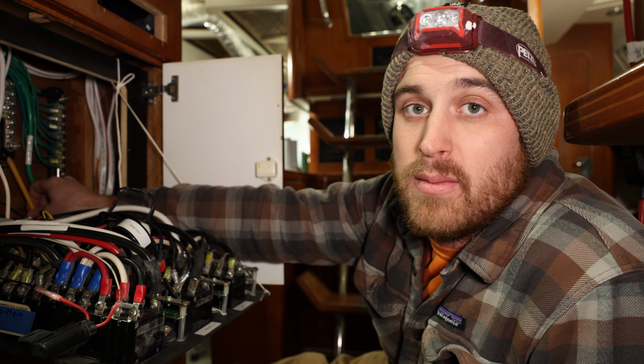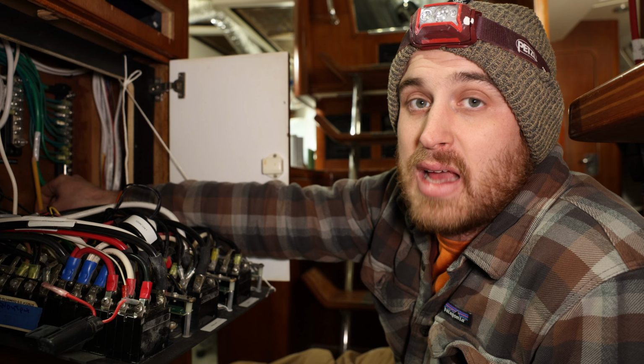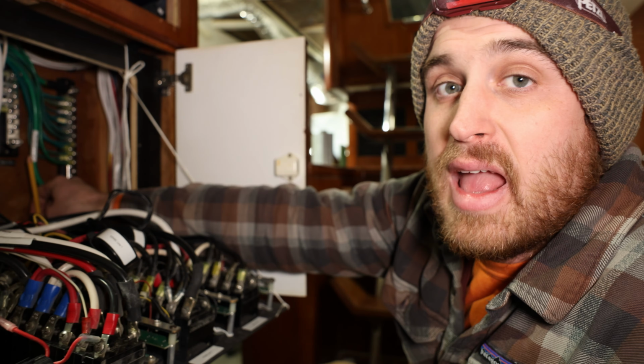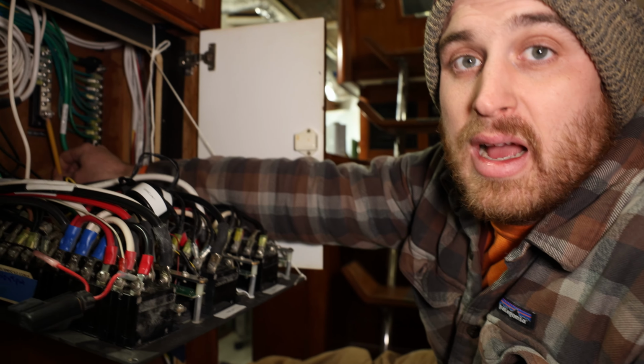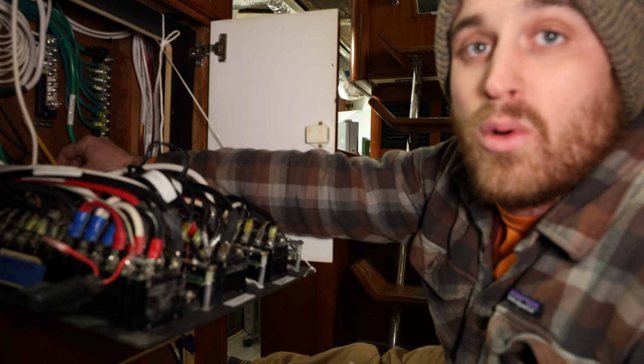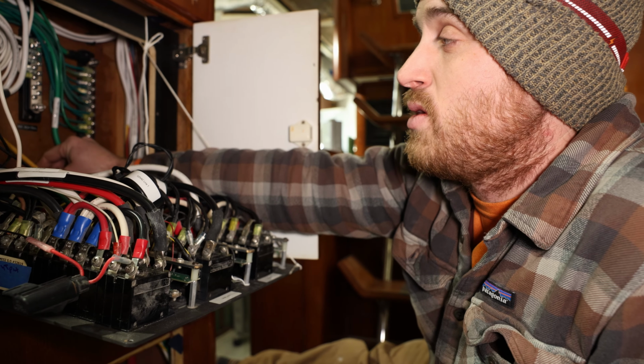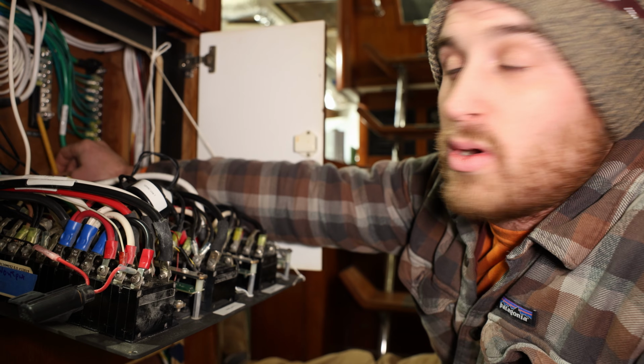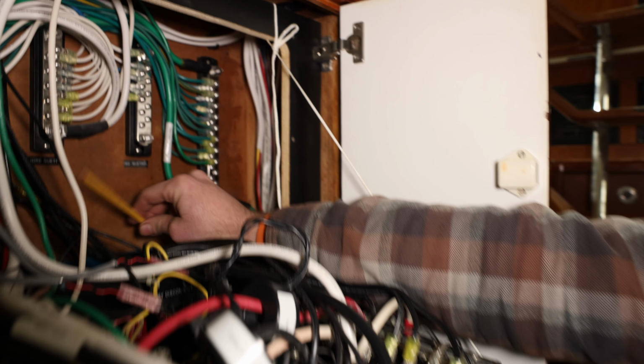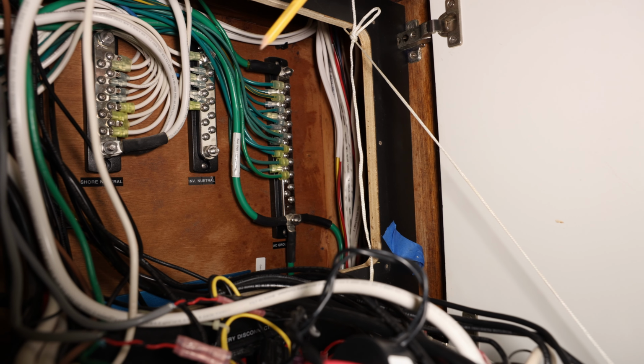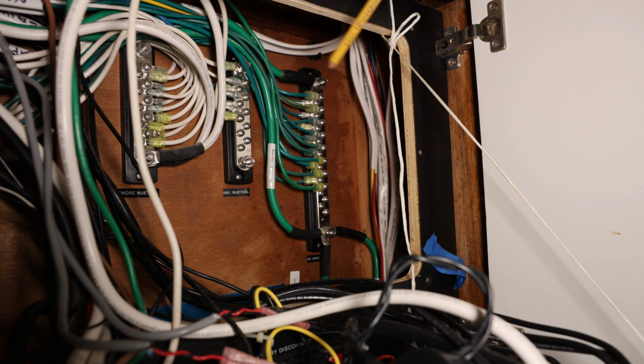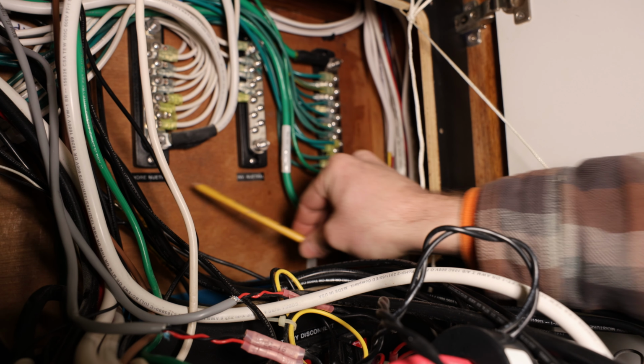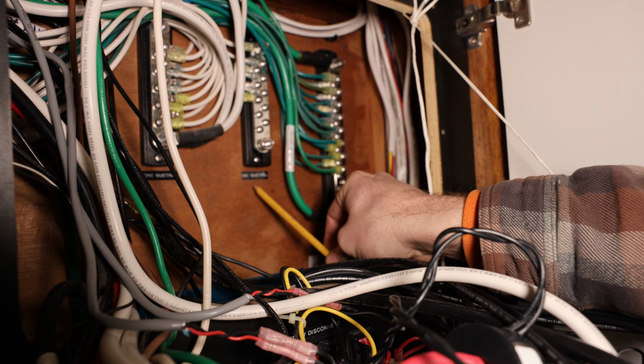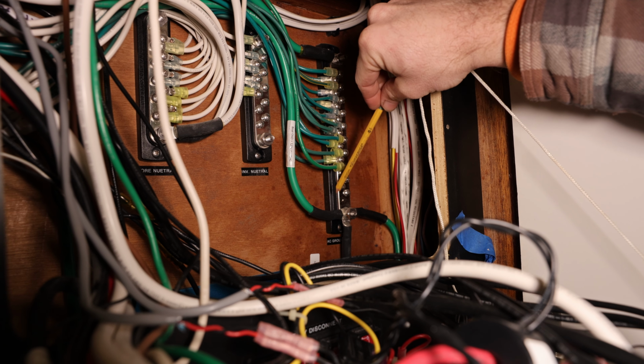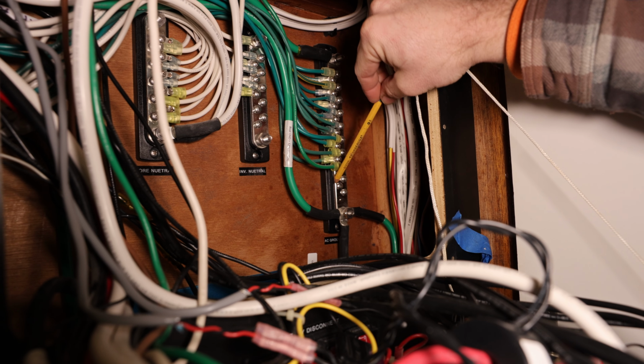So the only time the neutral and ground are bonded is at the source of the generator, and for our new design it'll be at the source of shore power, using an isolation transformer. But before we get to that, a couple cool things the older system had besides the separate shore neutral and inverter neutral: this is the AC ground, the safety ground bus.